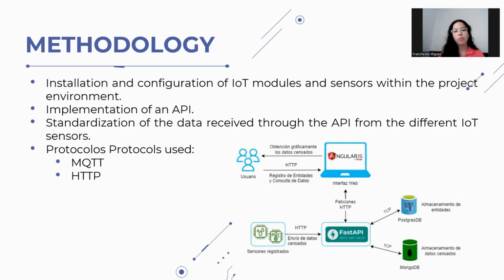It uses two protocols. The first one is MQTT for bidirectional communication and HTTP for data transfer. The sensor data is logged in a PostgreSQL database via the API, including a unique sensor identifier and a JSON field with the sensor data model aligned with the project Haystack's tagging standard.